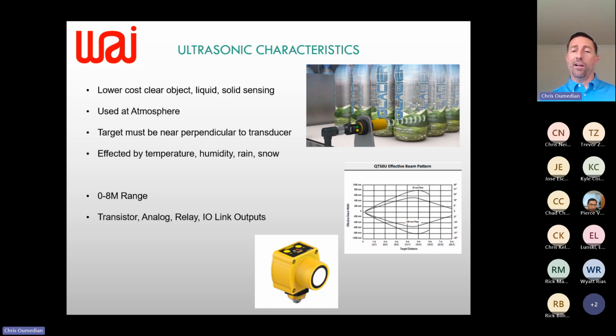The other thing to be aware of is that beam sort of looks like a football if you go out to the range of the sensor. You want to be aware of what we call the effective beam width - on your screen you'll see that football shaped pattern, which is the sound wave. You want your target within that beam, with no obstructions inside it. So if you're in a vessel, you need to make sure your effective beam is more narrow than the vessel, otherwise you get sound waves bouncing in directions you don't want.